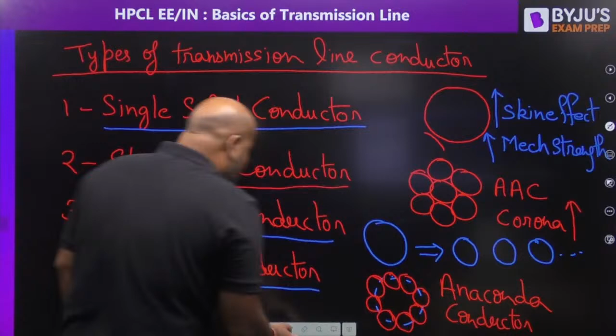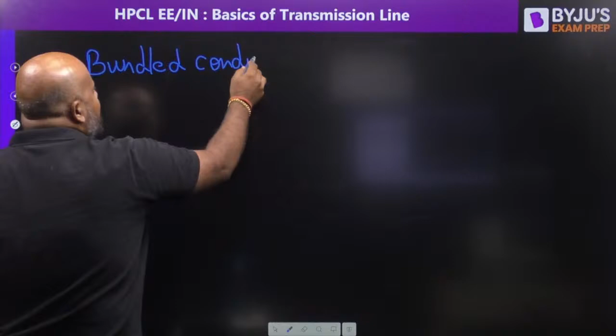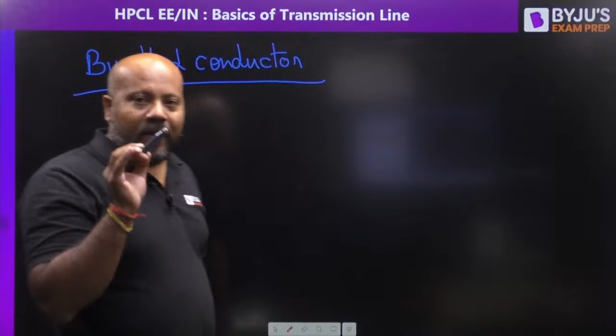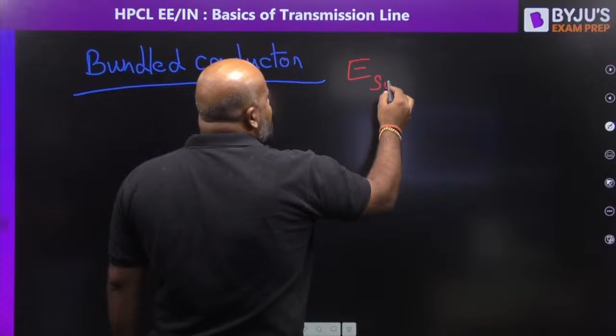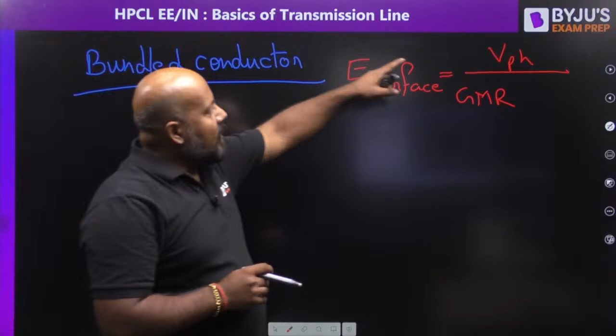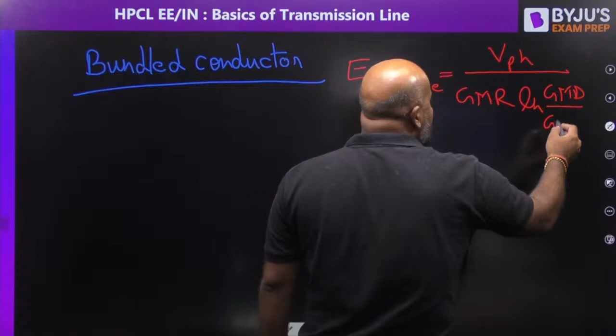Now our focus is on bundled conductors. The moment you hear the word bundled conductors, what is the first thing that should come to your mind? The major reason for using bundled conductor is to reduce the electric field stress at the surface of the conductor. The expression for electric field stress at the surface of the conductor is given as phase voltage divided by GMR ln GMD upon GMR. Now this is the logarithmic one, so it is not going to affect much.